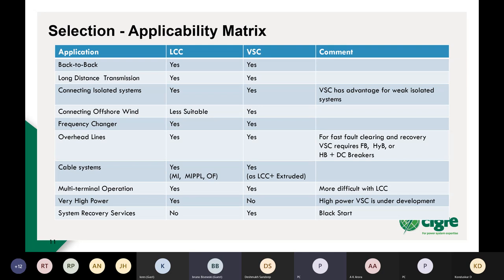Multi-terminal operation is easily possible with both technologies. A little more difficult with LCC and maybe more limited. Most of the multi-terminal operation with LCC so far has been limited to about three terminals. And there are, I think, some VSC systems now with up to five terminals and operating very well. For very high power, LCC still has the advantage, but VSC is under development, and it will very shortly reach, I think, the same level of power that you're getting with LCC. And for system recovery services, reactive power, black start, LCC is really not as flexible there as VSC. So the advantage there is with VSC.